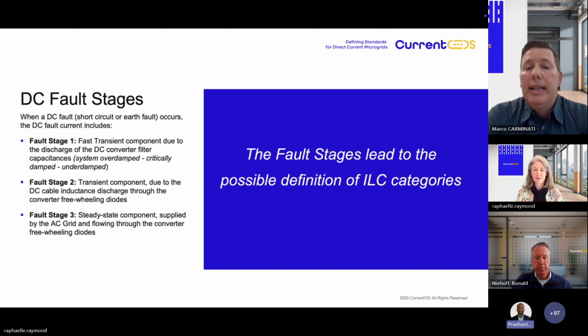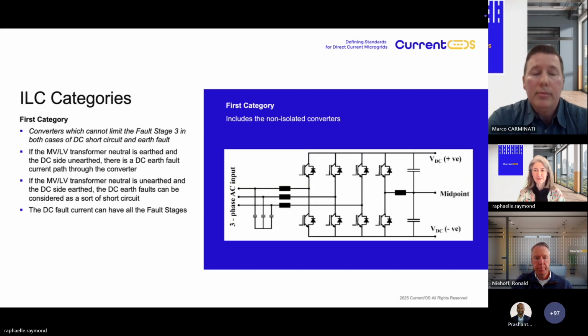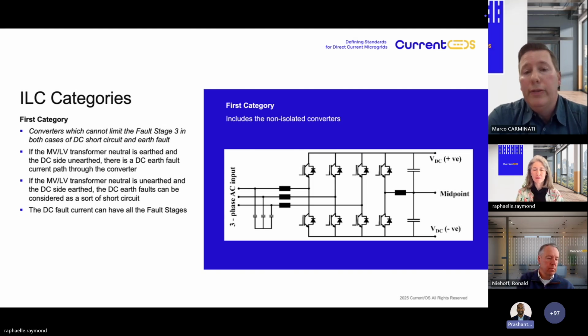As you can see, the fault stages depend on the type of interlink converter, and we have 3 ILC categories, as we'll see now. Here you can see the first category of ILC, which includes the non-isolated converter. Basically, in this category, the converters cannot limit the fault stage 3, in both cases of DC short circuit and earth fault. In particular, if we have a medium voltage, low voltage transformer neutral earthed, and the DC side unearthed, in particular the positive and the negative, there is a DC earth fault current path through the ground connection of the transformer.